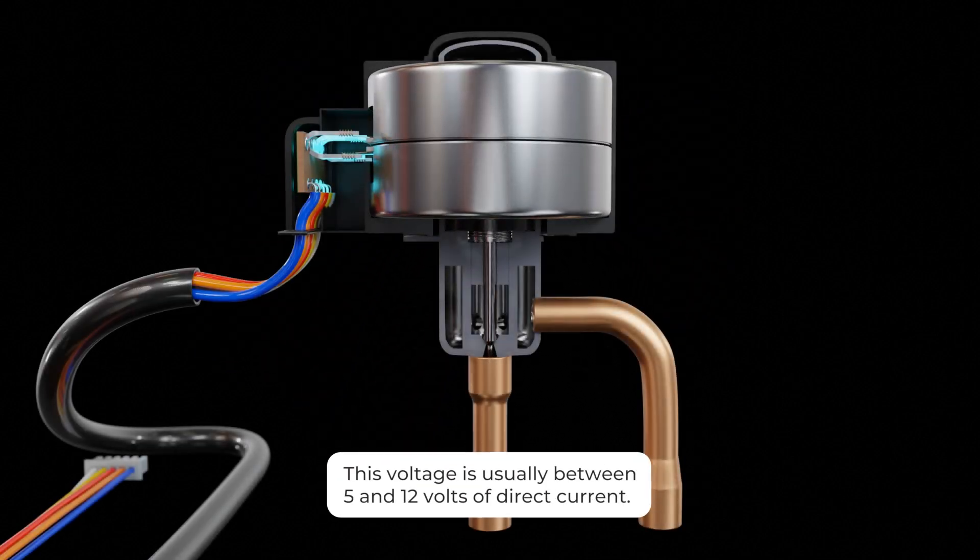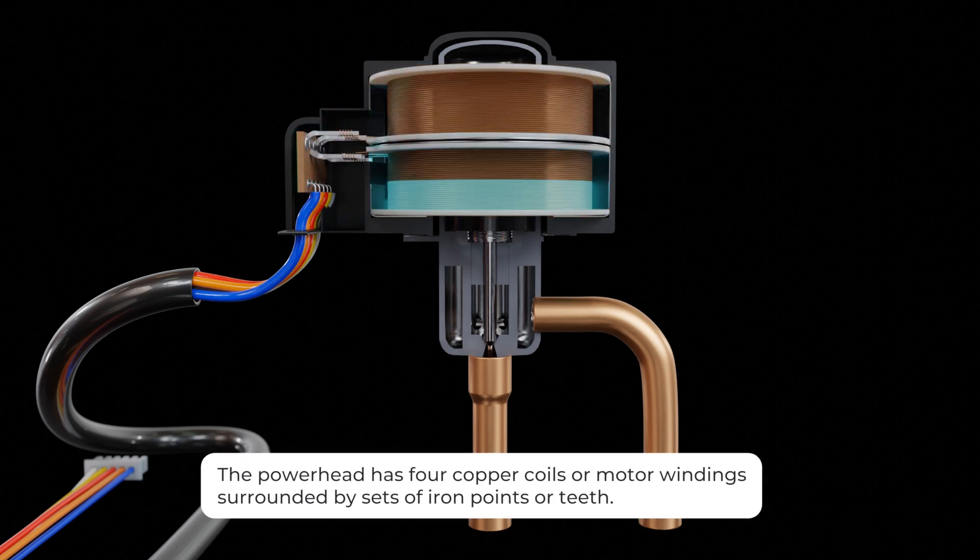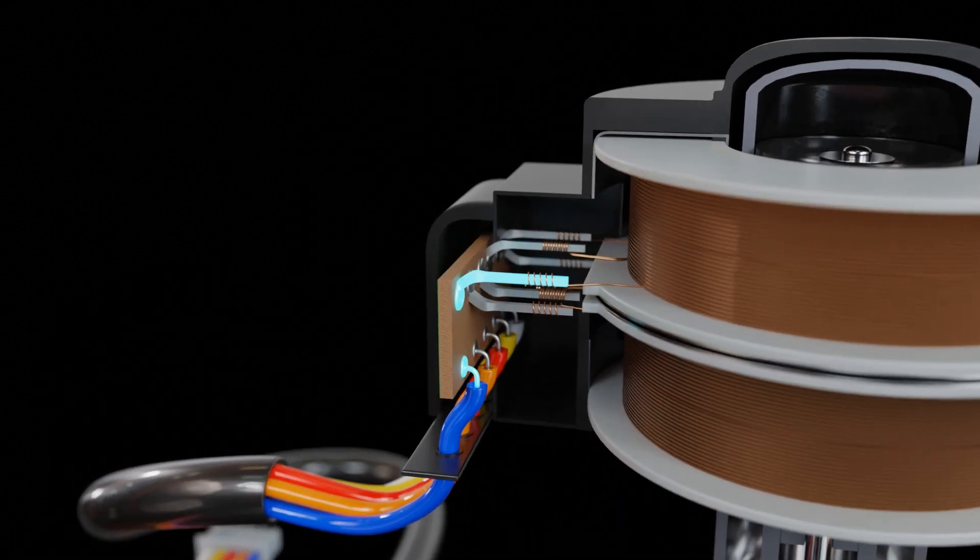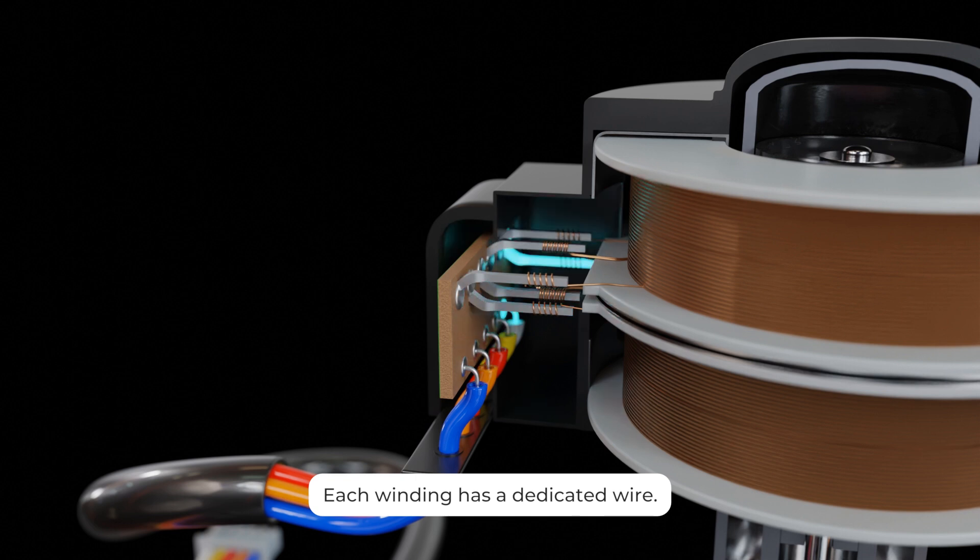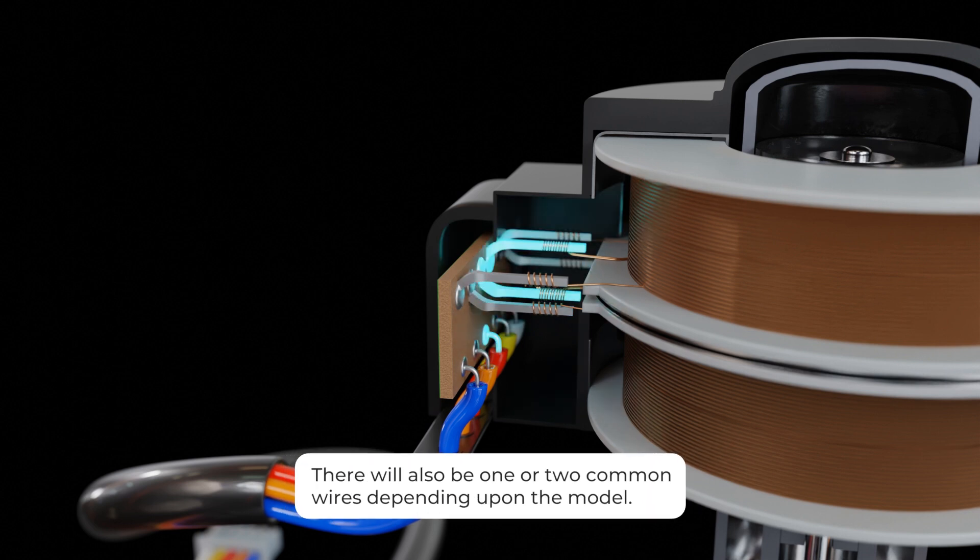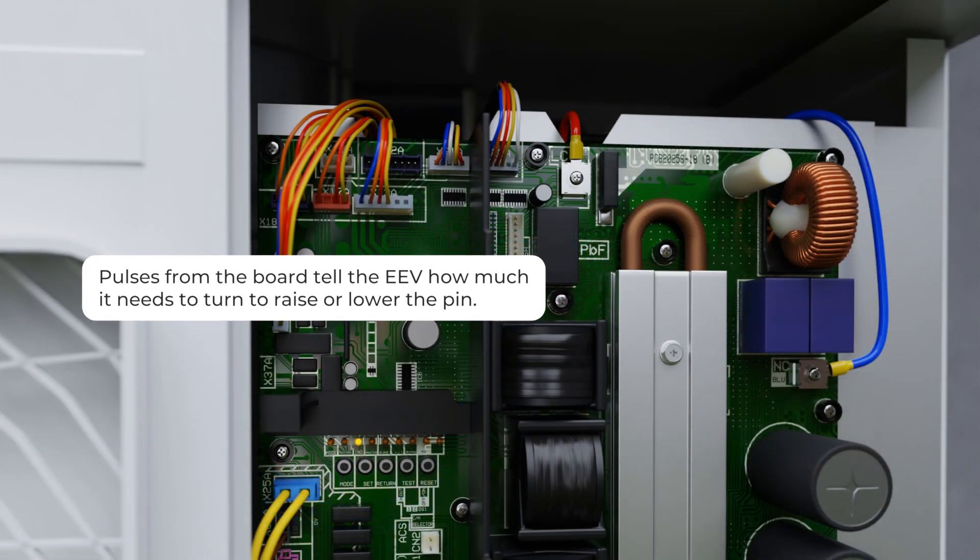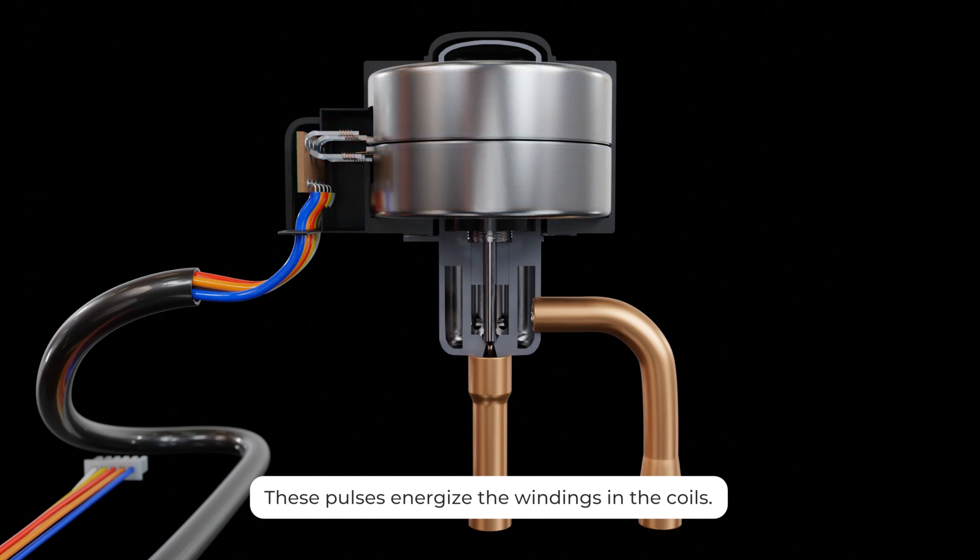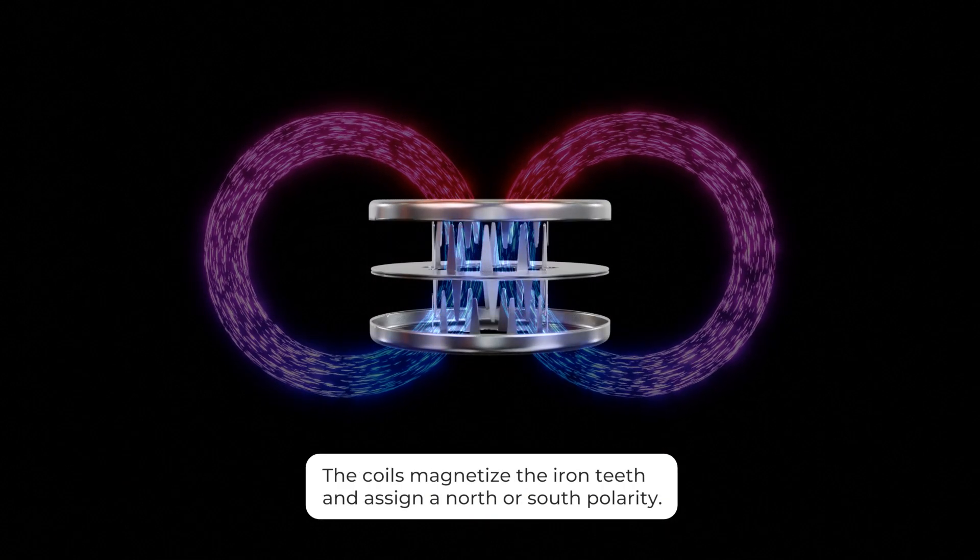This voltage varies by manufacturer but is usually between 5 and 12 volts of direct current. The power head has four copper coils or motor windings surrounded by sets of iron points or teeth which concentrate the magnetism in specific areas that allow the motor to turn with precision. Each winding has a dedicated wire. There will also be one or two common wires depending upon the model.